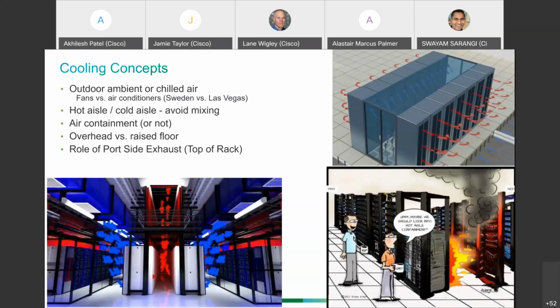There are a couple of things to think about with cooling. The first idea is hot aisle, cold aisle — it's very important to prevent hot air from mixing with cold air. You don't want hot air coming back over the top of the rack and feeding back into the system, creating a feedback loop that keeps getting hotter. Air can come from the top or the bottom. In our labs we just treat it like a regular air-conditioned room, but in a data center it comes down from the top or up through holes in floor tiles.